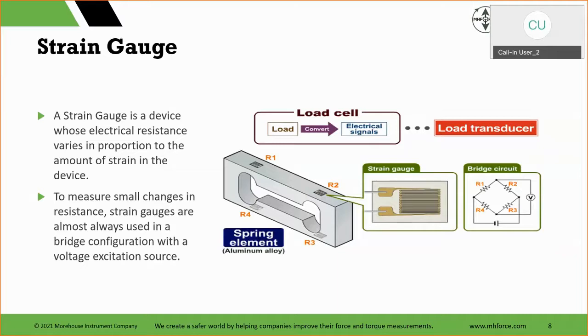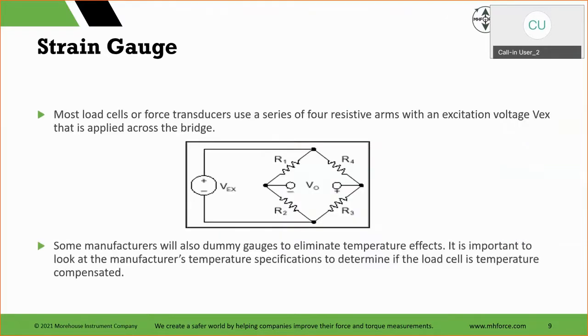And we issue a lot of millivolt per volt reports with the ratio measure, so it's taking the millivolt and dividing it by the DC voltage. And that's how the circuit is. So it's a device whose electrical resistance varies in proportion to the amount of strain in the device. And to measure small changes in resistance, strain gauges are almost always used in a bridge configuration with a voltage excitation source. Most load cells or force transducers use a series of 4 resistive arms with an excitation voltage that is applied across the bridge.